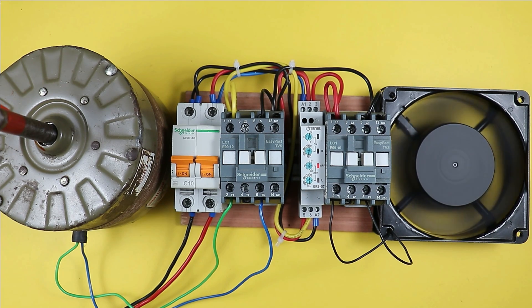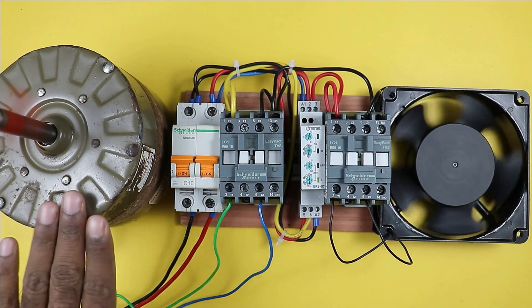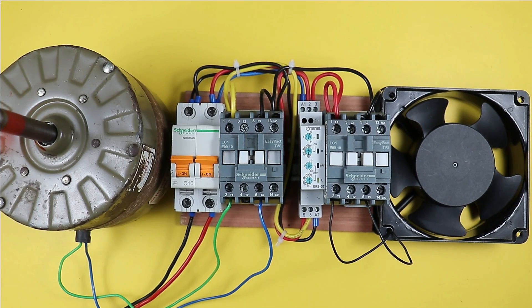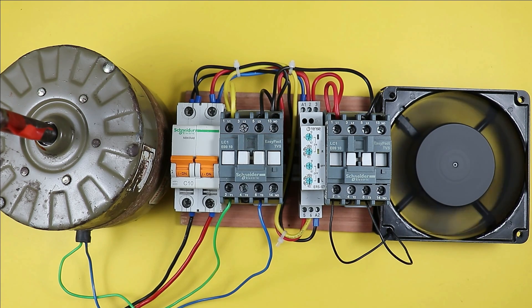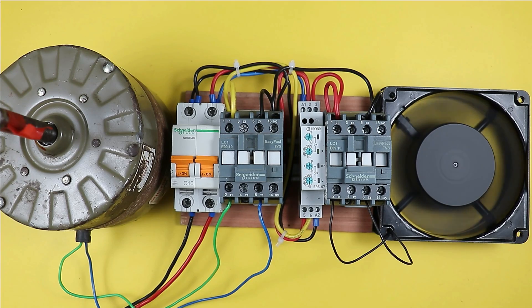When the MCB is turned on, the first motor turns on and remains on for 10 seconds as programmed. After 10 seconds, the first contactor turns off. It remains off for 5 seconds, then the second motor turns on and also runs for 10 seconds. When those 10 seconds are completed it turns off, and after 5 seconds the first motor turns on again — and so the cycle continues.